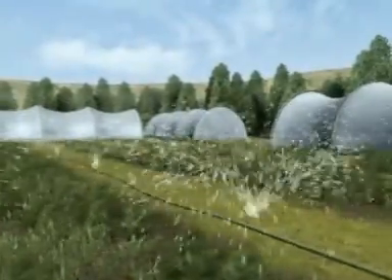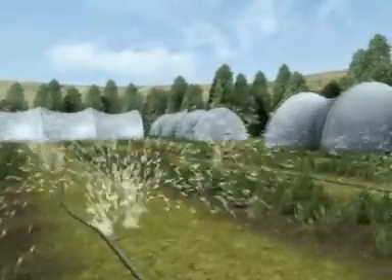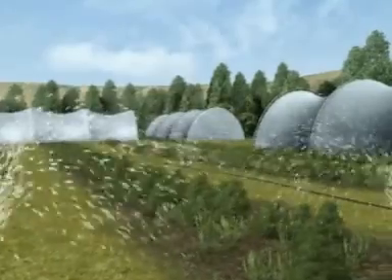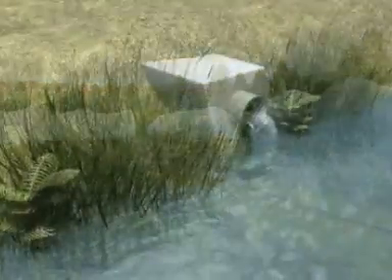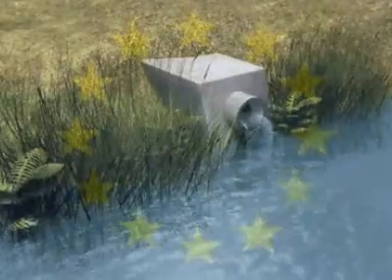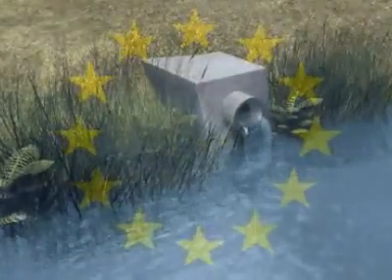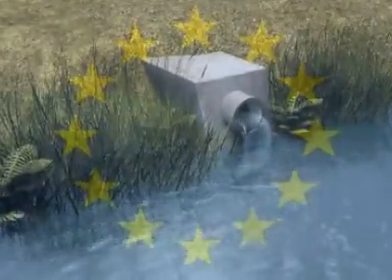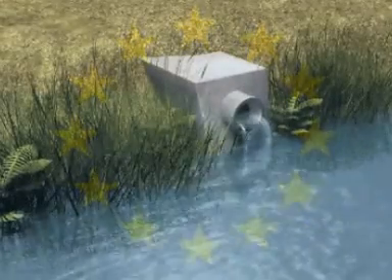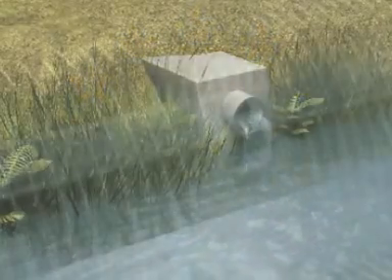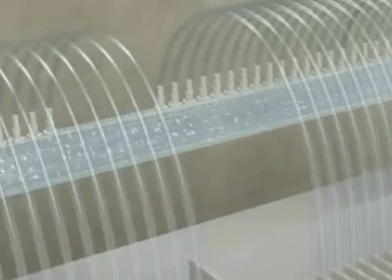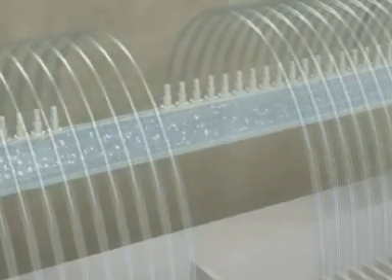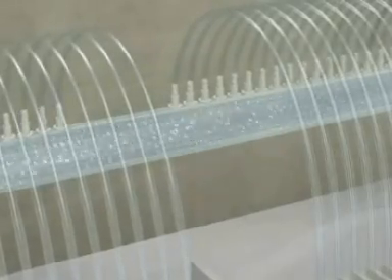The removal of these pathogens enables the treated effluent to be reused or safely discharged into watercourses or aquifers. For the treatment of normal domestic wastewaters, the undiluted permeate satisfies the European Union Bathing Water Directive for bacteriological limits and also complies with the World Health Organization standards for unlimited irrigation. Permeate can be collected either using gravity head or a low-pressure suction system. The optimum gravity head is approximately 1 meter.